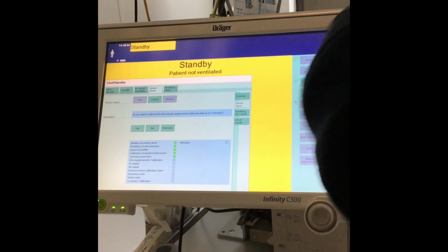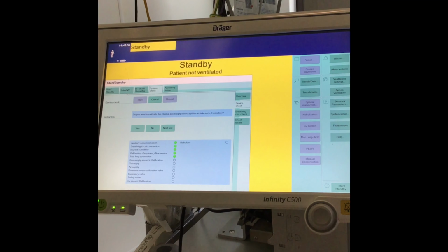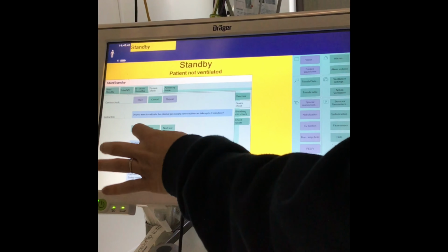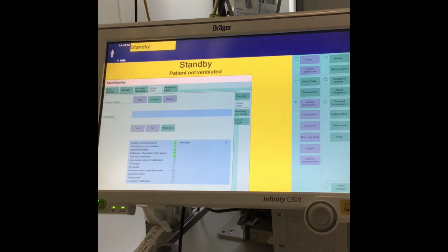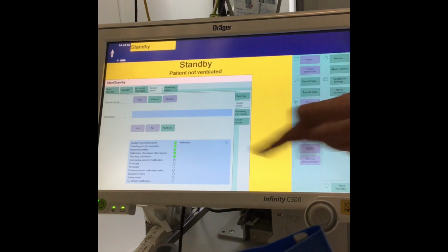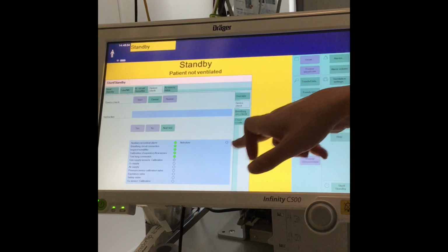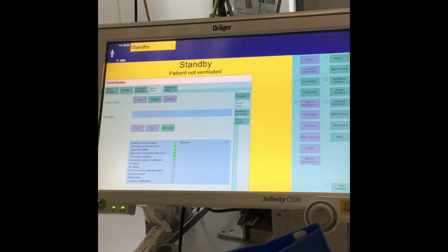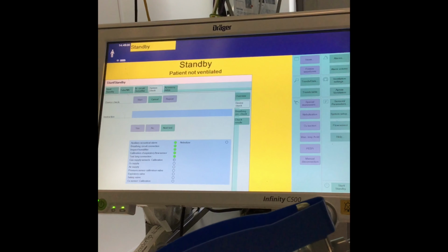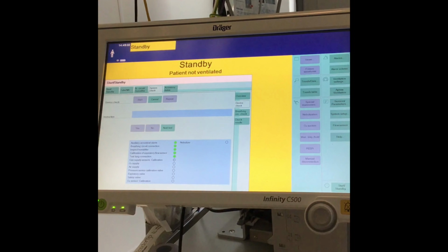Now this, do you want to calibrate the internal gas supply sensor? This doesn't have to be done every check, but if it does need doing, it will prompt you to tell you that it needs doing. But for the sake of the video, we'll just hit yes. What you want to achieve when you're checking the ventilator is that you want to have all of these circles with a green light in. If there is a red light, it means that something's failed and it needs to be looked at before the patient can be connected.